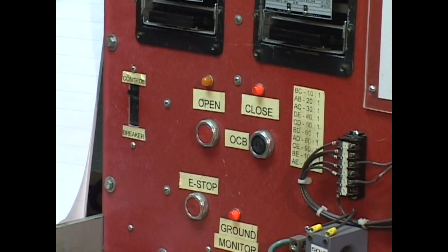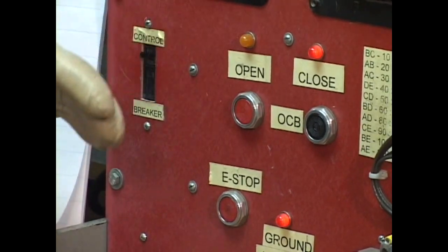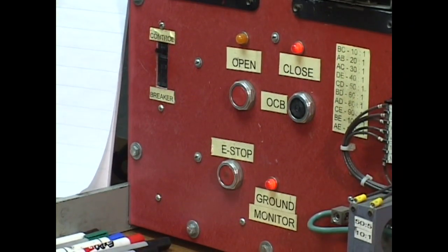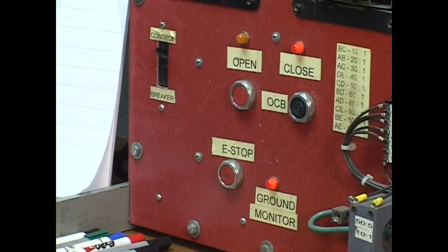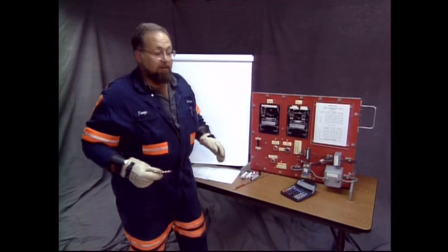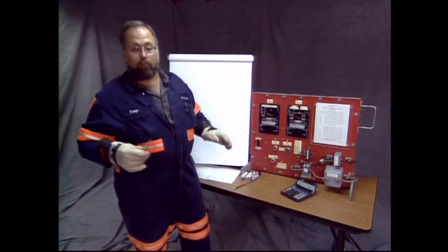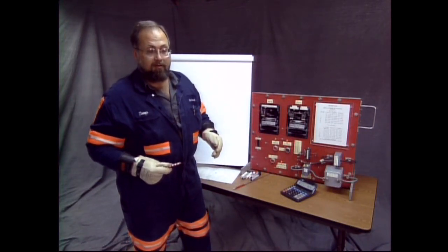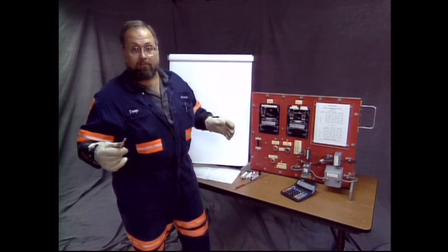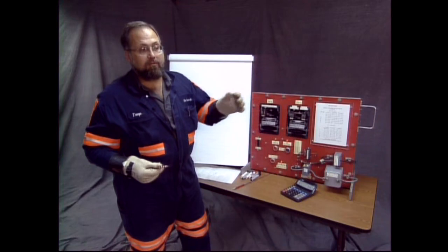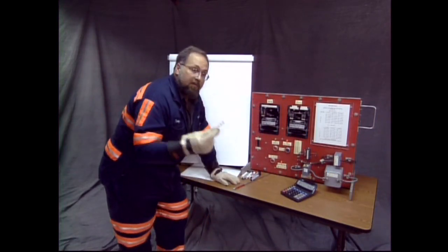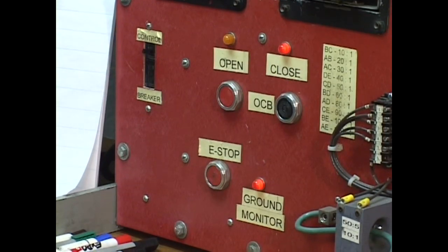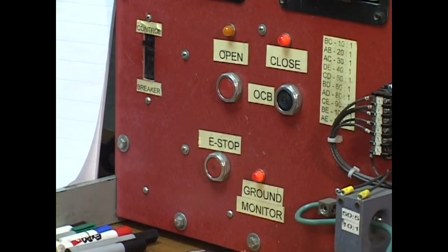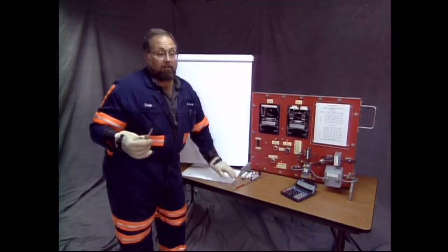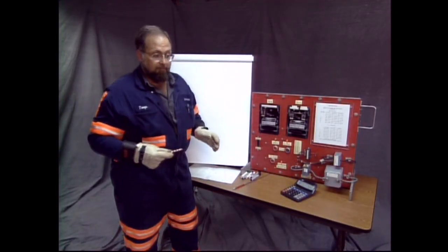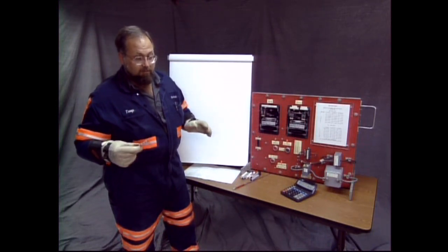The last test. Now here on this test panel on the trainer, the E-stop that you're going to operate to prove ground continuity is right here. But in real life, what you're going to actually be doing as part of your job, the E-stop will be at that farthest point, at one of 2 places, at the next high voltage relay panel or at the end of the line, where you have a high voltage input into a box and no feed through. And you're going to operate the E-stop at the furthest point controlled by this breaker and protected by this breaker to prove ground continuity. Now, a lot of people make a mistake of saying, I'm going to check my E-stop at the furthest point. That's not what you're doing.